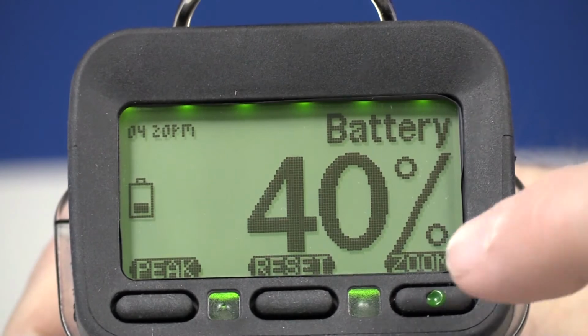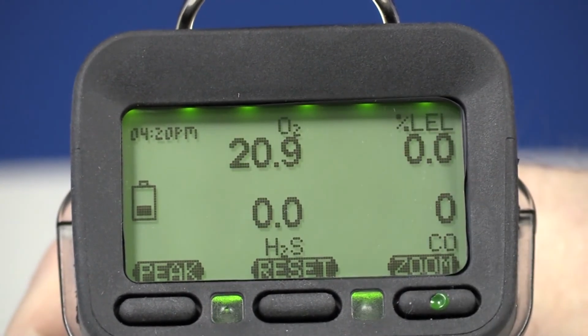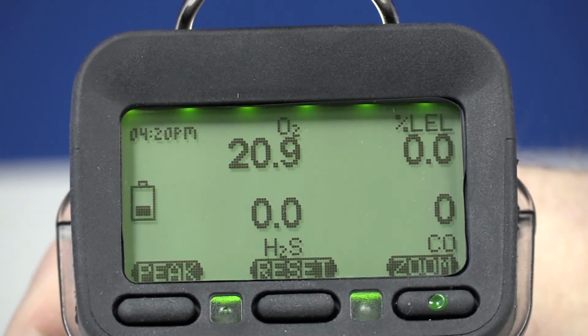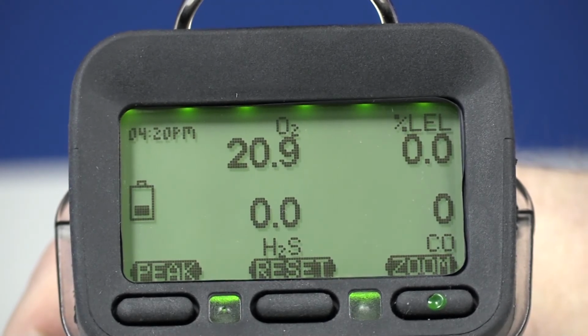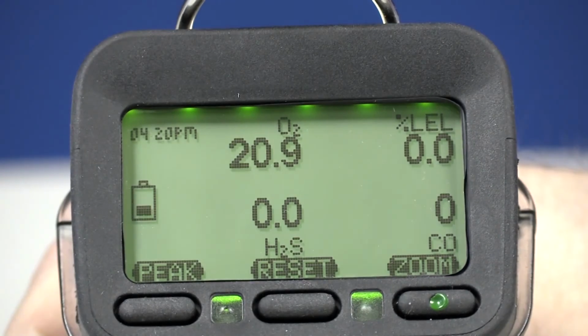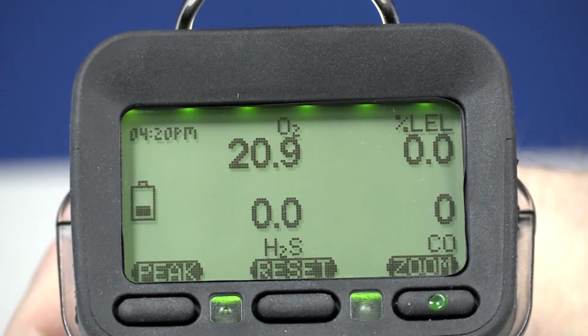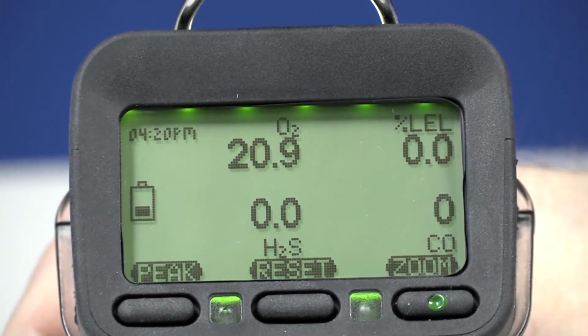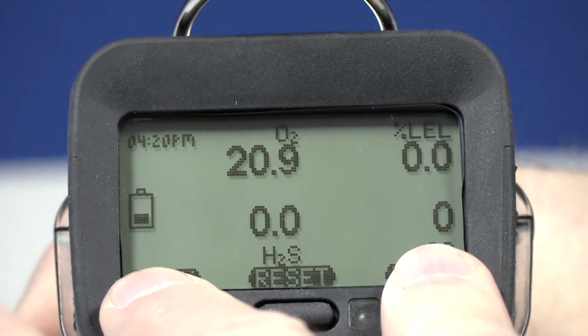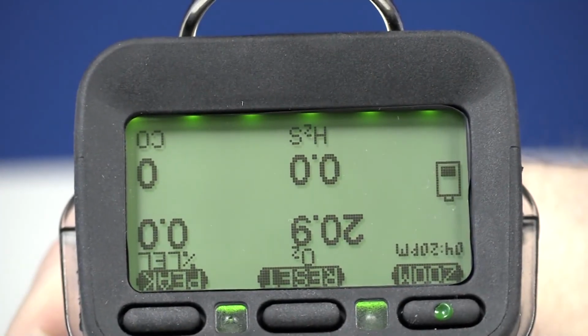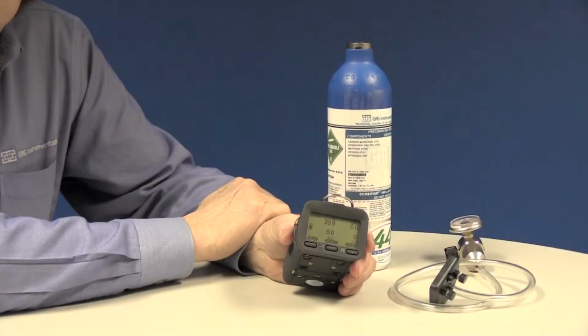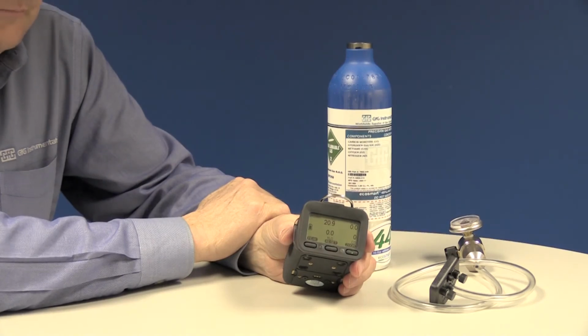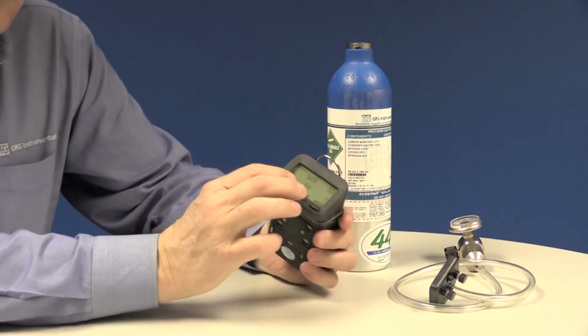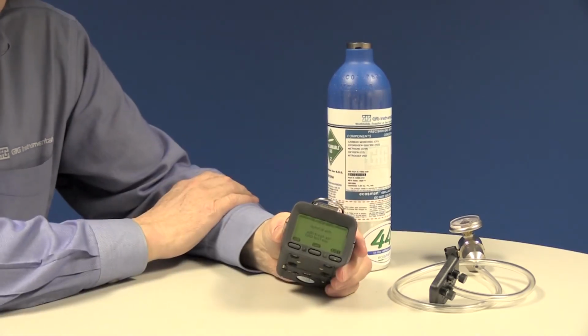Pressing any button momentarily turns on the backlight. Press zoom once to make the numbers larger. Press zoom again to see the next gas. After a period of time, the display will return to the normal view, which shows readings for all 4 sensors at the same time. Pressing the peak and zoom buttons at the same time is used to flip the display orientation. Pressing the reset and zoom buttons at the same time puts the instrument directly into the AutoCal calibration mode.